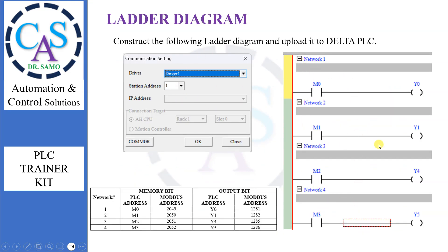Now let's move to the ladder diagram. Construct the following ladder diagram and upload it to Delta PLC. Here, we are using memory bits M0, M1, M2, and M3. Remember the Modbus addresses of these memory bits, because these addresses will be used in HMI designing. The Modbus address of M0 is 2049, M1 is 2050, M2 is 2051, and M3 is 2052. The station number should be selected as 1 because it is a slave device. We set the address of HMI as 0 because HMI is the master device.